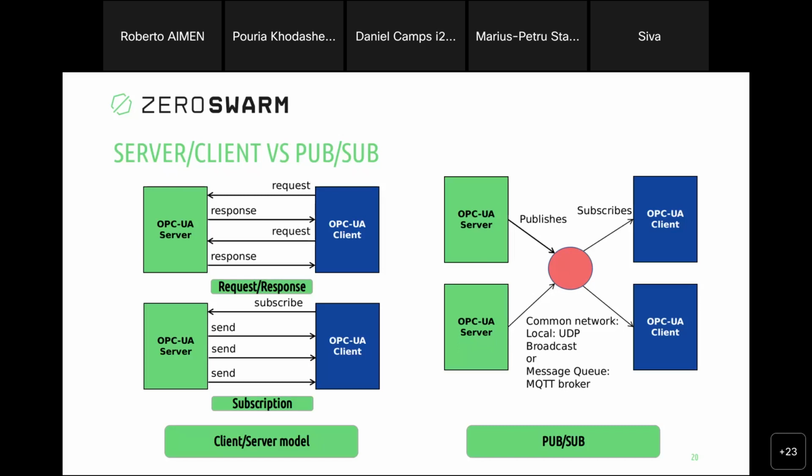The first aspect which we covered was communications and creating an OPCUA FX connection, which means two PubSub connections, because PubSub is only a unidirectional PubSub connection object type. And if you also want an answer or keep-alive, connectivity which you need very often in industrial automation, you need to have it in the reversed way too. So then we created the FX connection notion. This is creating two PubSub connections, one in one direction, the other one in the other direction.